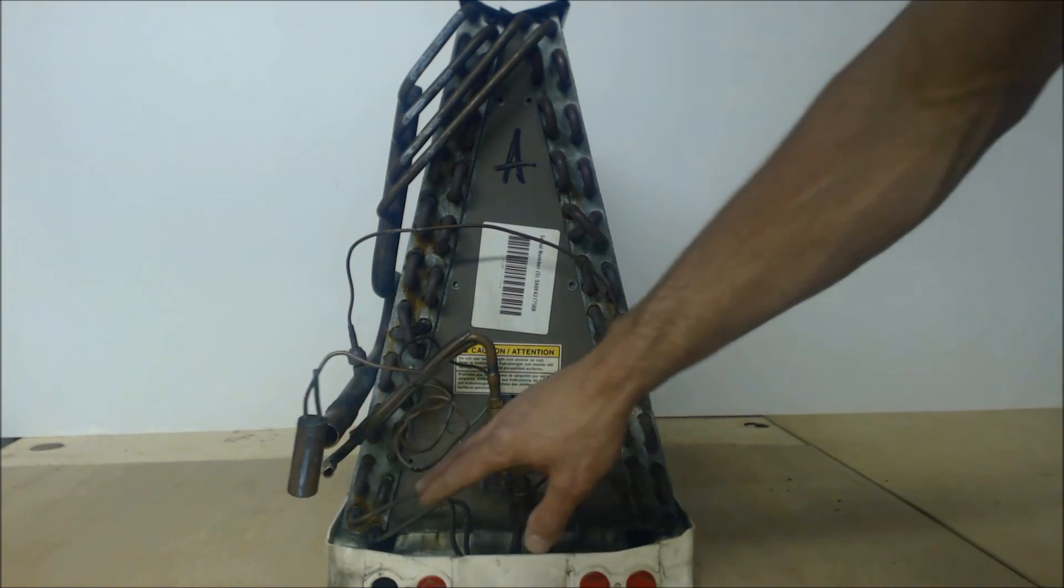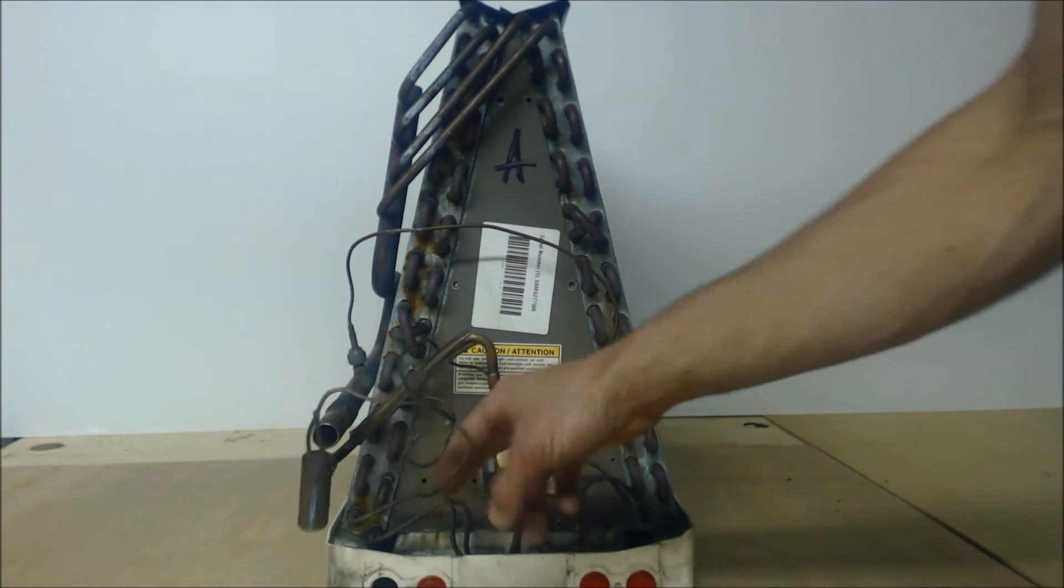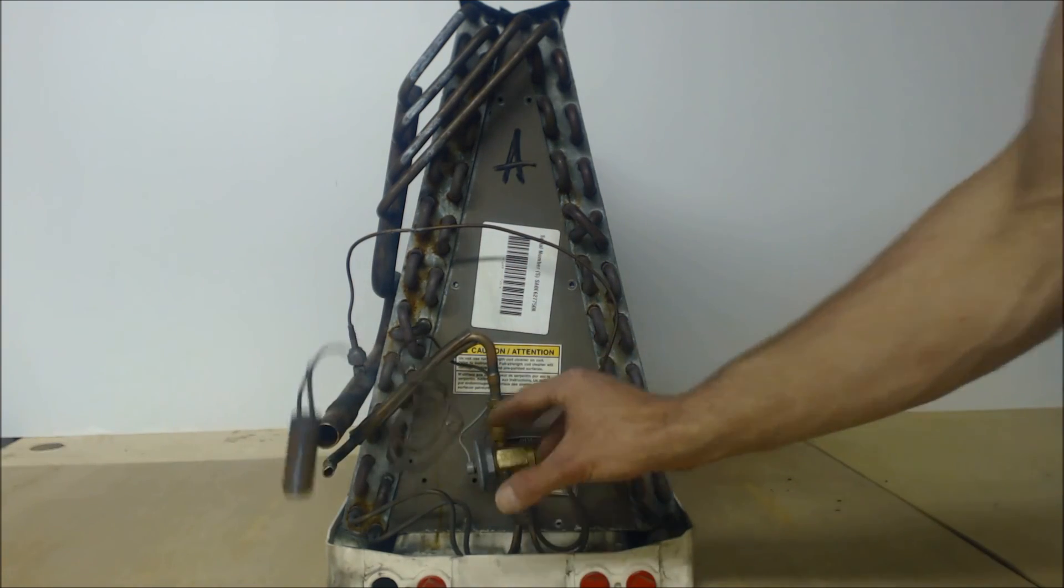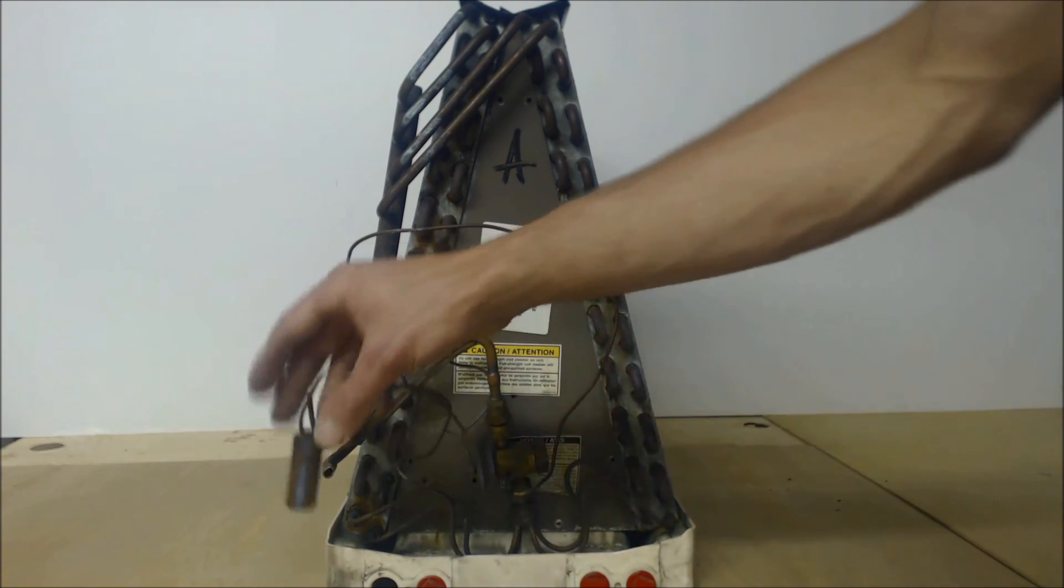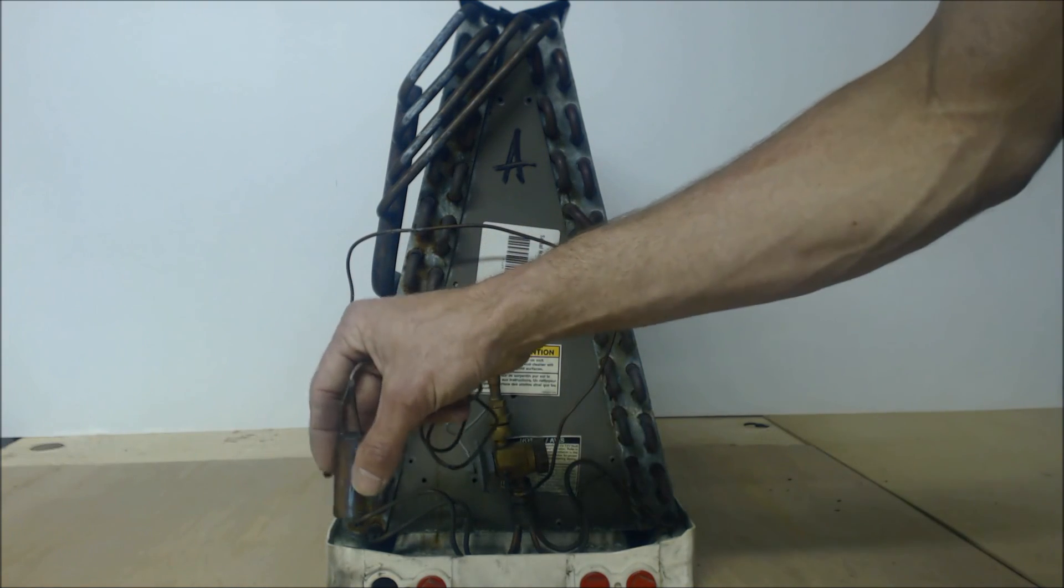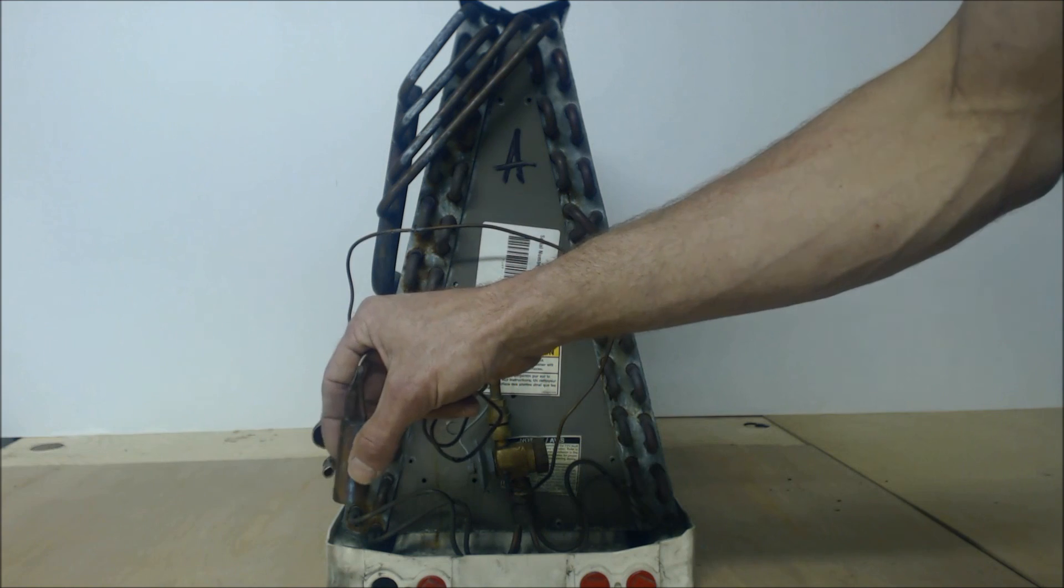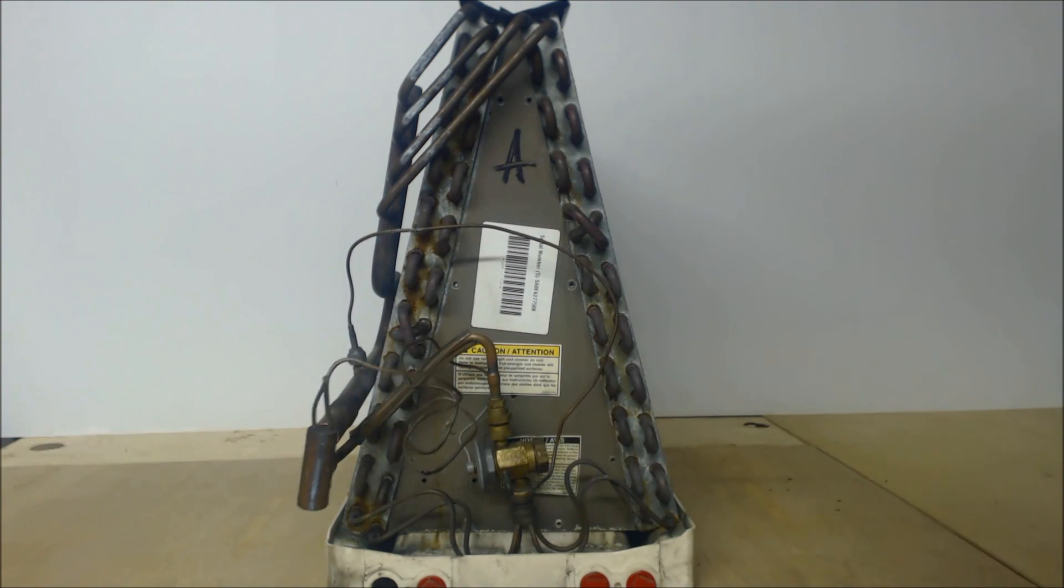If this runs out of refrigerant, then there will be no more pressure to apply to the TXV in order to open. So if you see a suction pressure that's down lower, that's because there was no opening pressure due to the refrigerant loss in the TXV bulb.